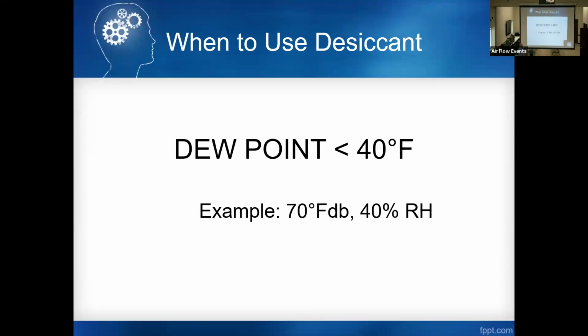Typically, you'll use desiccant when you need to get below a 40 dew point, 70 degrees, 40% RH, where your traditional mechanical system just can't get down that far.